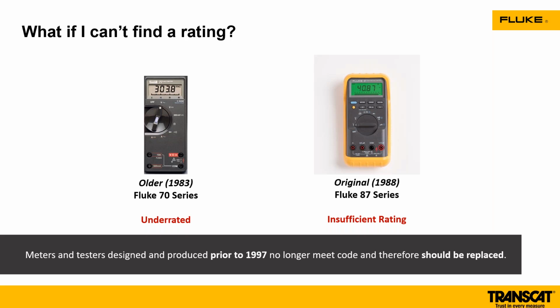Even the original 1988 Fluke 87 series, still an amazing meter, doesn't have the right rating for it. I highly recommend if you have these meters prior to like 1997, they no longer meet that code. You need to get them replaced for the new environment that we're in. You can still use these meters, but use them in those category 2 environments. I highly recommend that. But once you get into the other ones, you want to get a different meter.